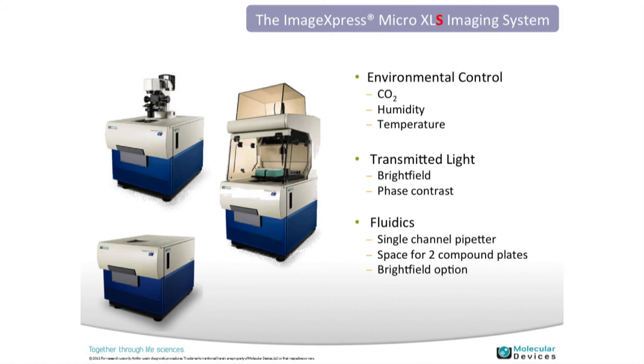A couple of options for the ImageXpress Micro: one is environmental control, which enables long-term live cell assays by controlling for carbon dioxide, humidity, and temperature — mimicking an incubator environment. We've had customers maintaining cells inside the instrument for up to seven days. There's also a transmitted light tower for label-free imaging, and fluidics, which can be used for fast kinetic reactions where you add a compound and immediately view the effects, or for any media change during a long-term experiment.